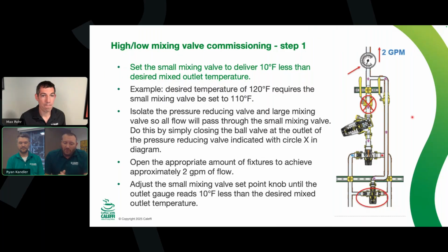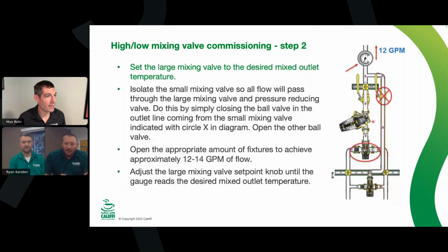First you want to focus on your smaller mixing valve. You isolate the big mixing valve and the PRV, then go around and turn some fixtures on to get 2 GPM flowing. Then adjust that smaller mixing valve to 10 degrees less than your set point - for example, if your set point is 120, you'd want that smaller mixing valve set to 110. Then here's step 2.